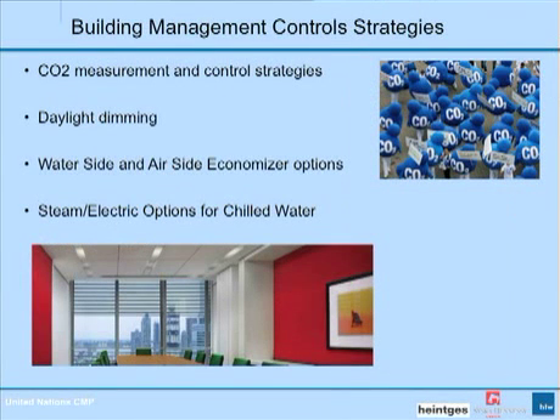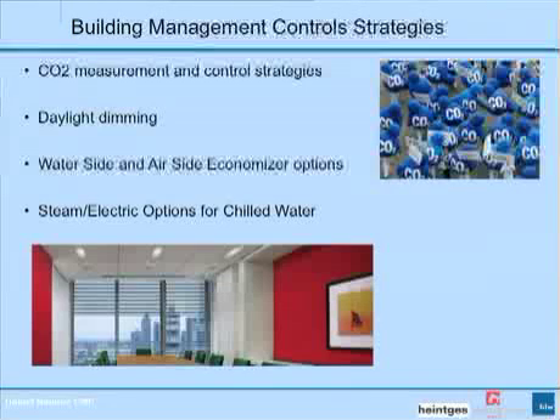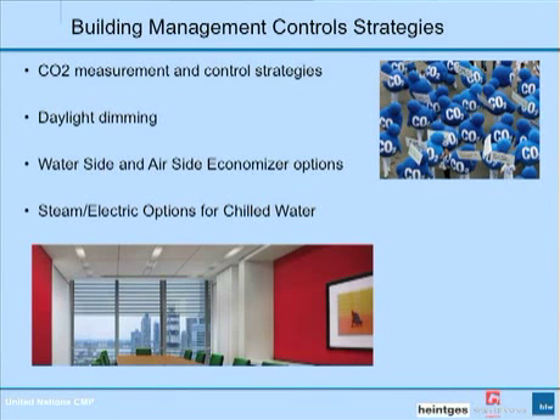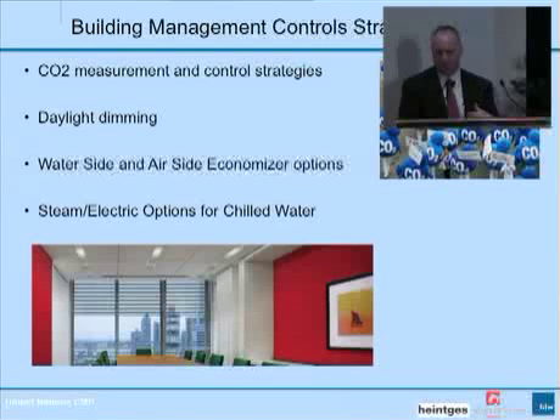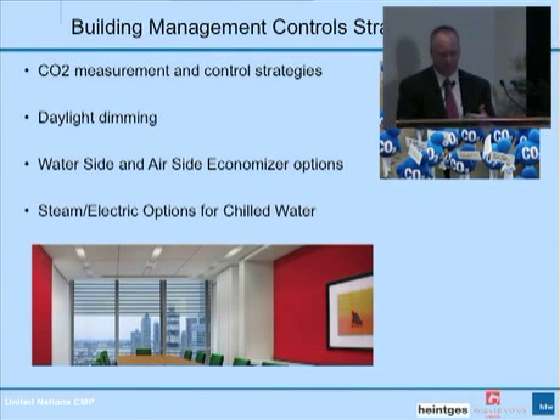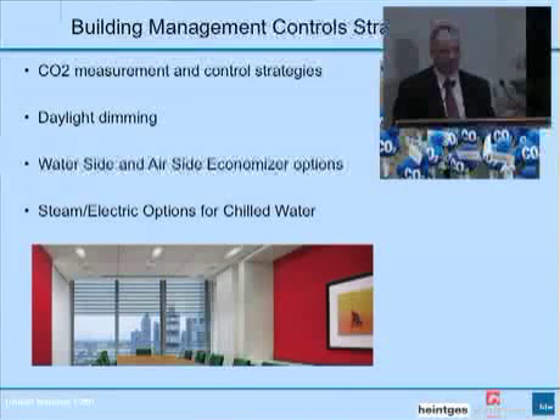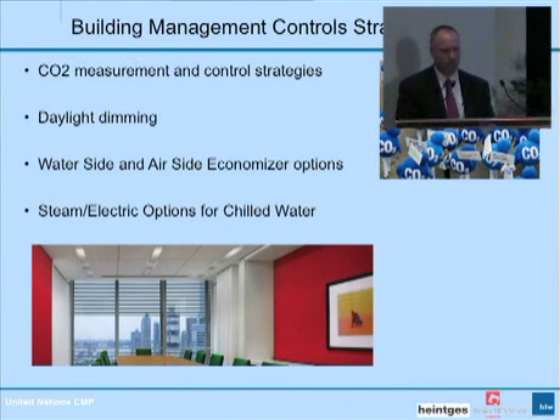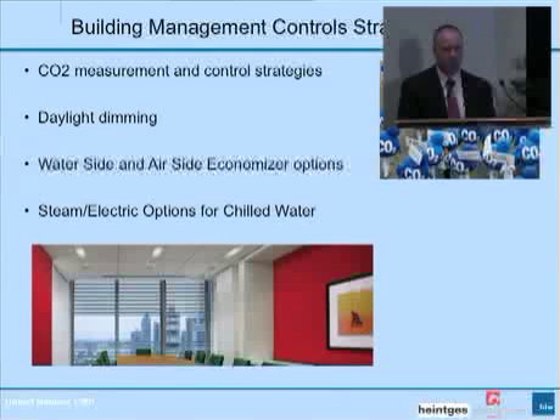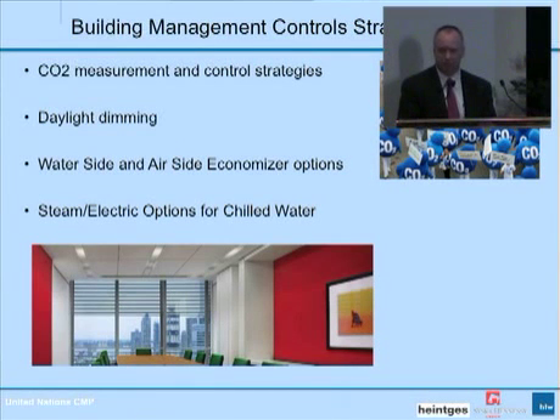The building management system itself is incorporating many of the latest control technologies. We're using CO2 to measure all the occupied spaces throughout the campus. We're adjusting it to increase outside air when we find that the level of CO2 within the campus is worse than what is typically available outside. And when we find that the building is not loaded, we're throttling that all the way down. If a typical outside air component of an air handling unit might be 20%, we'll bring that all the way down to 5% if we're capable of measuring that with the CO2 sensors.